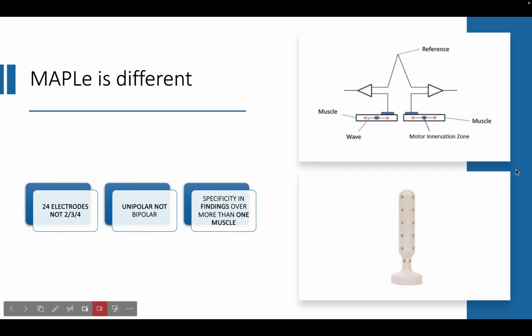So you can find the EMG results are specific to each muscle, and you can find different information for different muscles rather than a summary of findings that is then found simply on a graph. So as an example, with a bipolar, using the Piriform Plus as an example, where you have two large electrodes that span multiple muscles. Those two electrodes will combine and compare their scores across the muscles, and you will get a simple line graph that will tell you the average of that muscle activity or underactivity or overactivity within the pelvic floor as a whole. Whereas with the Maple, the individual electrodes will compare their findings with the 0 point, the reference point, and you will get an absolute score for that muscle.